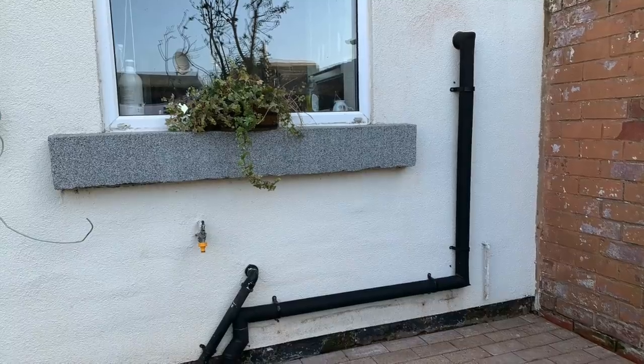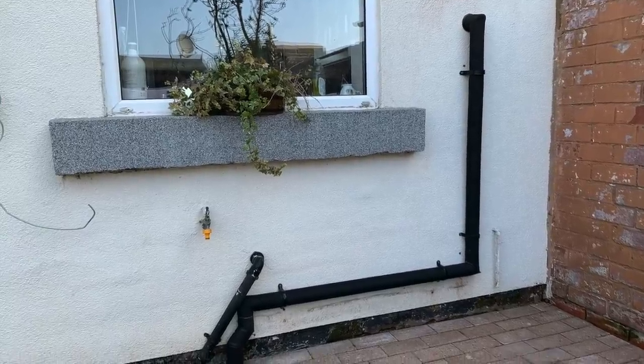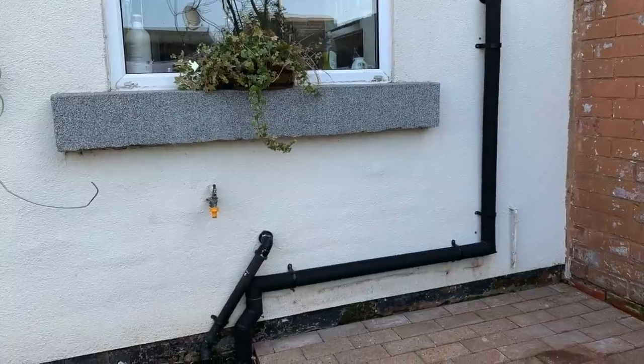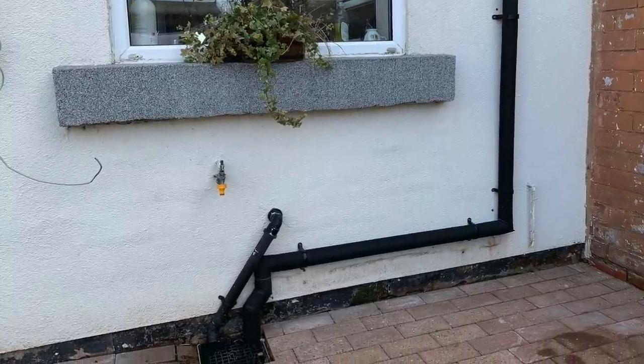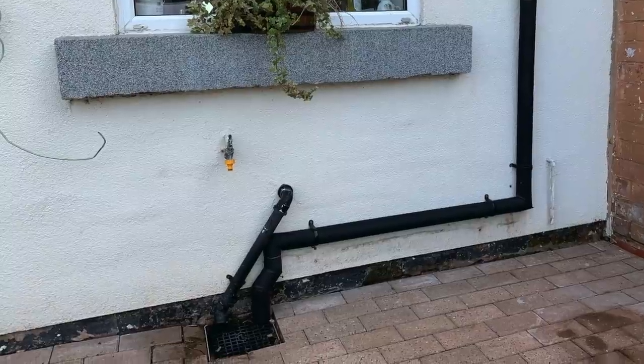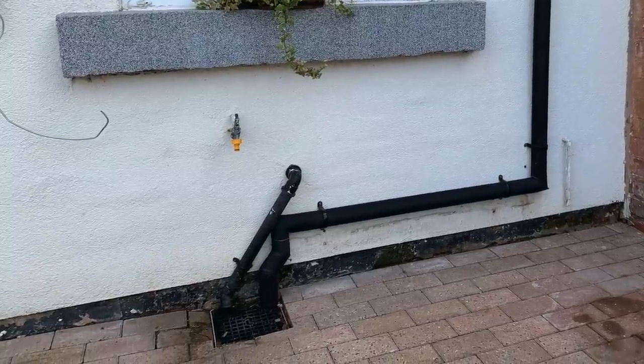externally at all now. External condensate pipes need to be a minimum of 32mm, and again only run for 3 meters, but they have to be insulated with class 0 insulation according to the building regulations, but we're going to look at that a little bit closer in a little while. We'll come back to the insulation shortly.